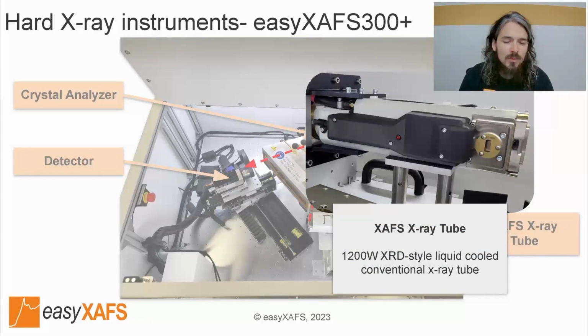For the X-ray tube, we use a 1200 watt XRD-style liquid-cooled X-ray tube. We use either a silver or a molybdenum anode, depending on the measurement. In our case, we aren't using the characteristic lines from the anode. We're using the smooth broadband output from the Bremsstrahlung portion of the X-ray tube spectrum. As this style of tube is commonly used in XRD systems, the technology is reliable, proven, and low maintenance.